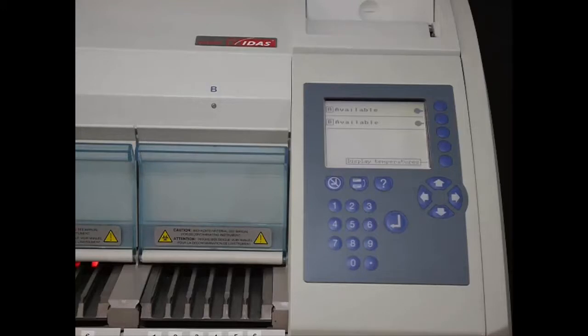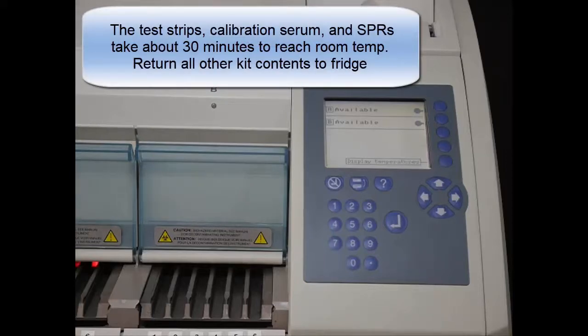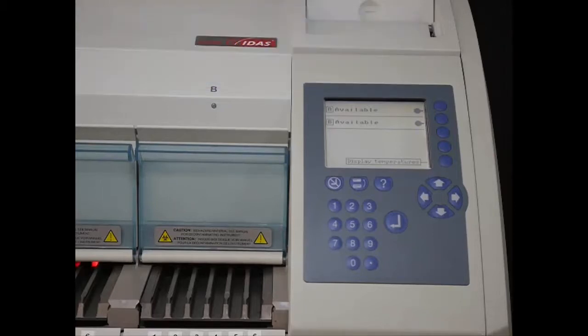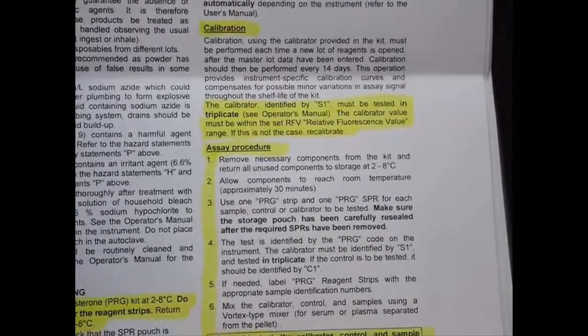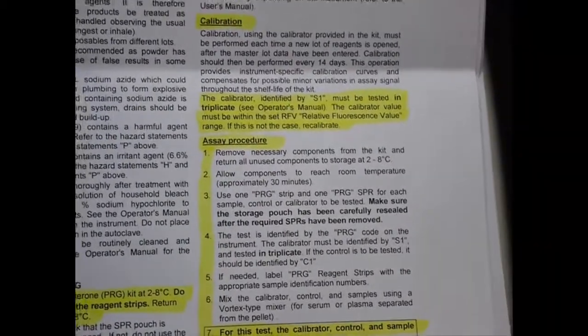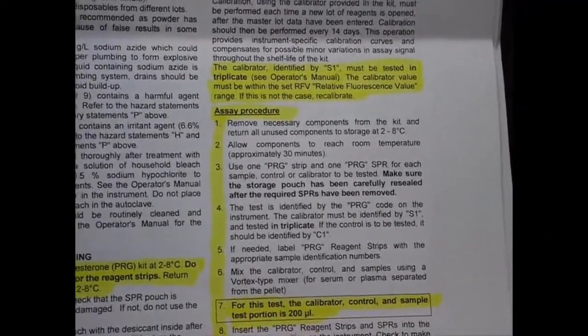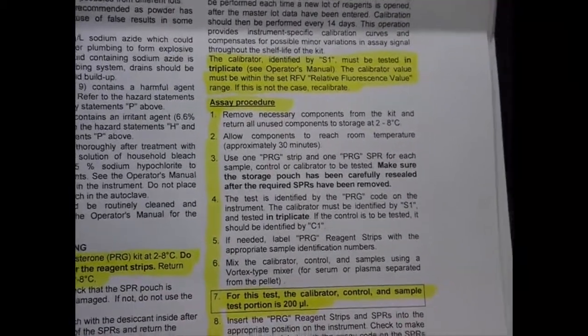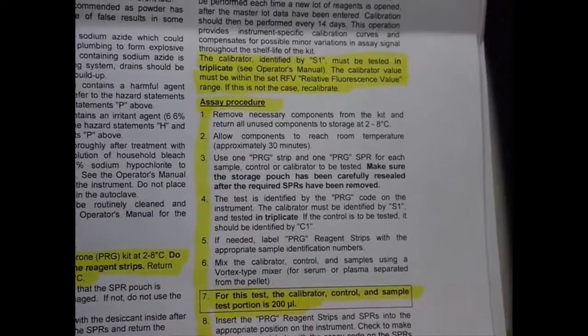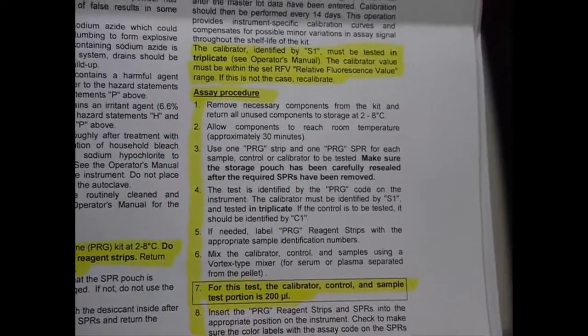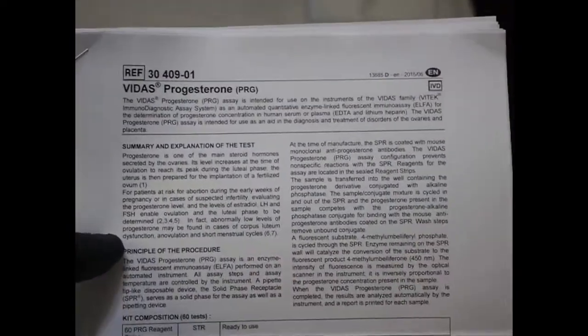The next step is to take 3 test strips and 3 SPR receptacles out of the kit and maintain at room temperature. You also want to remove the calibrator so that all the kit components are at room temp prior to running the calibration. For PRG, or progesterone, the calibration is run in triplicate. This just means that 3 test strips and 3 SPRs must be used in order for the calibration to pass. Different assays may have different procedures, maybe quadruplicate or just duplicate. Always refer to the assay insert sheet for the instructions.